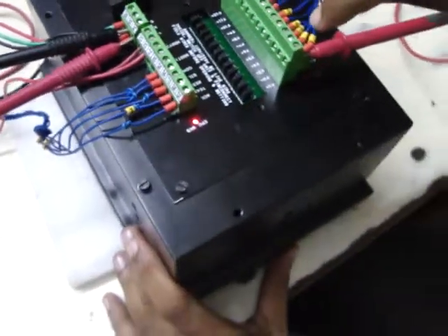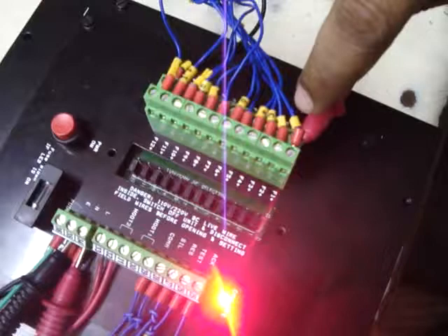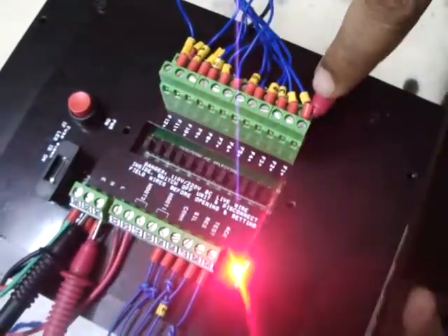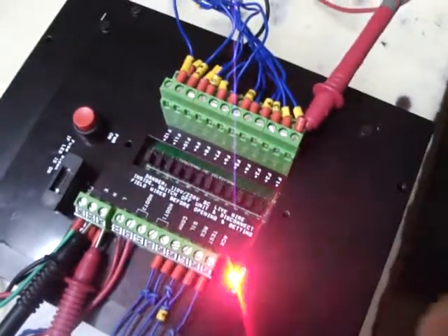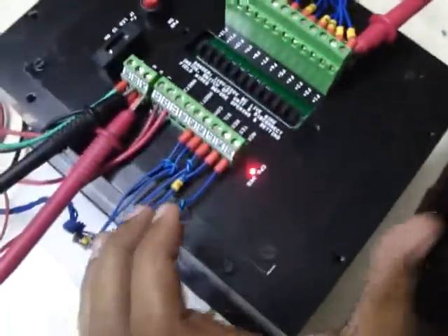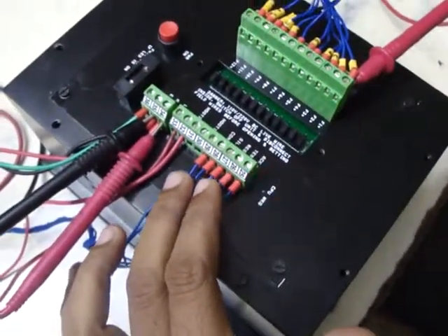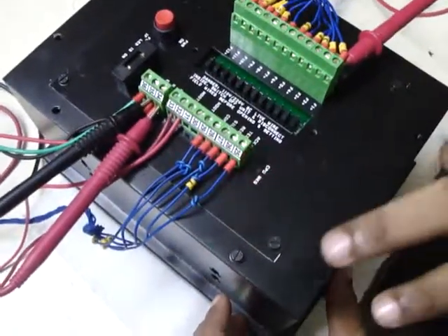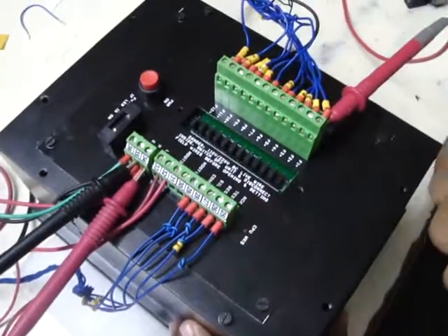Now, for each individual window, if 220 volt DC or 110 volt DC, based on the jumper selection, is available, the specific window will start to flash. There will be push buttons provided for acknowledge, test and reset of the annunciator. When the acknowledge push button is pressed, the specific window will become steady and the hooter will turn off.